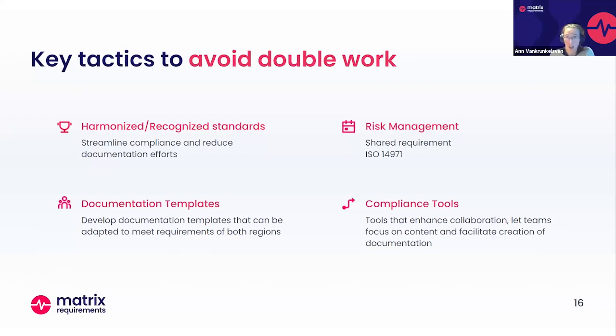That means that they are accepted to be a good way of working. So if you, for example, comply with ISO 14971, which is a harmonized standard and a consensus standard for risk management, then you know that if you follow that standard, it's an accepted way of doing risk management. So you can do this for several standards. And if you can make use of those standards, first of all, you have certainty that they are accepted. But secondly, if they are accepted in the different regions, it will avoid double work. You don't have to have two systems in parallel, one for each region. So it will reduce the documentation efforts if you can make use of standards that are accepted in all the regions that you want to target.